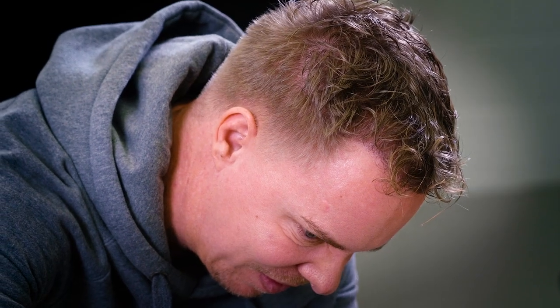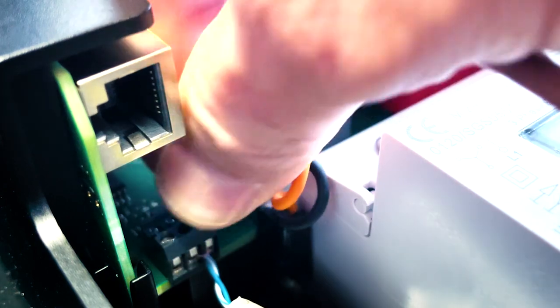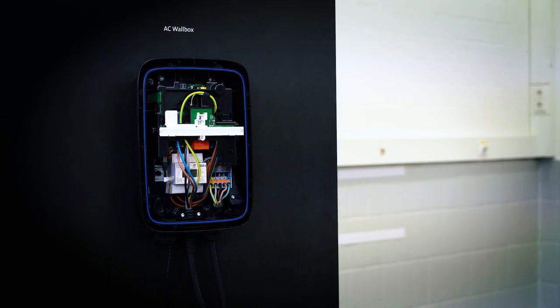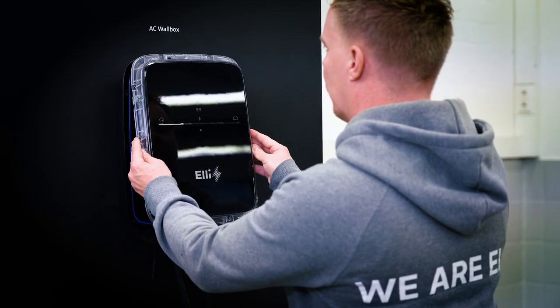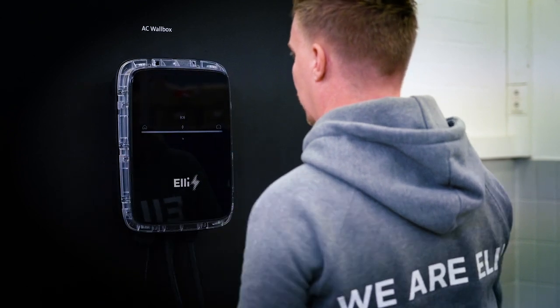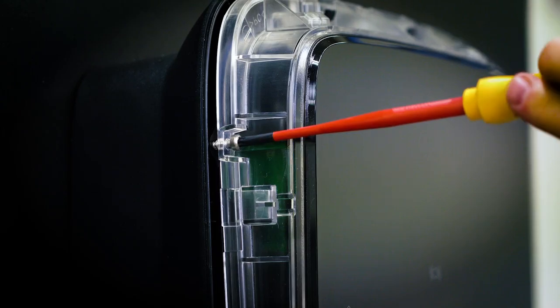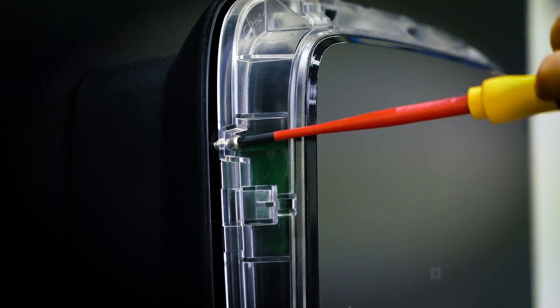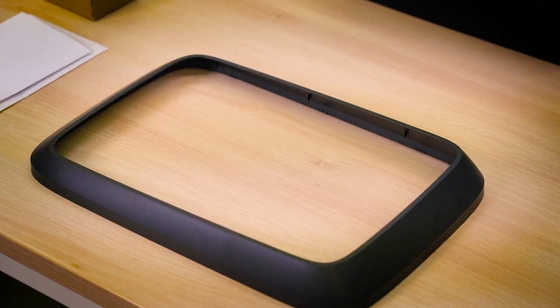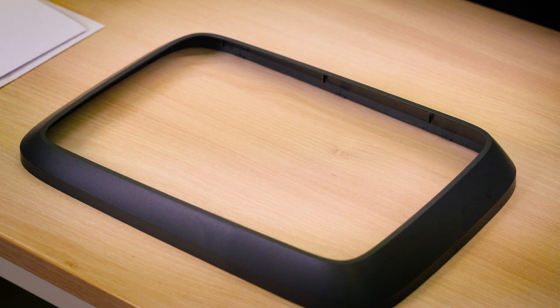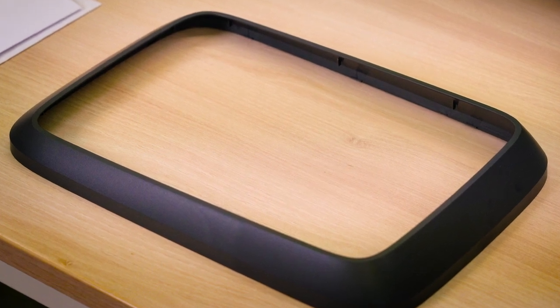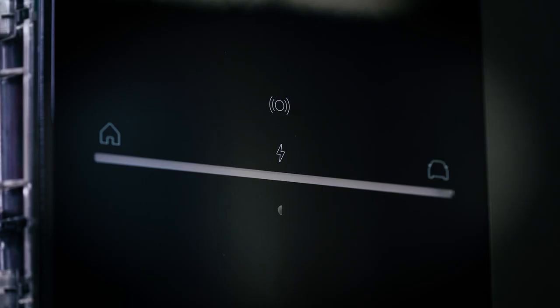For a Modbus connection, strip about 5 mm of insulation from a suitable cable and connect it to the supplied screw terminal. Then plug it into the appropriate port on the internal board. Attach the cover by hanging it over the two hooks at the top of the main unit. Then fold it down and clamp it in place. Finally, tighten the screws. Do not install the decorative panel until the wall box has been completely installed and successfully tested. To put the Elli Charger 2 into operation, follow these steps.